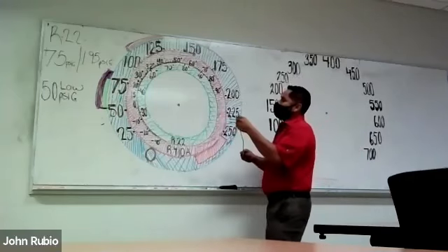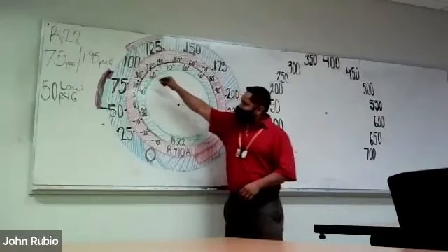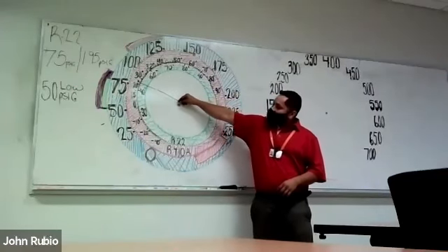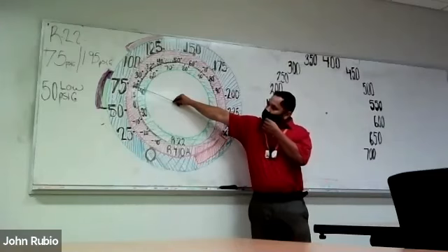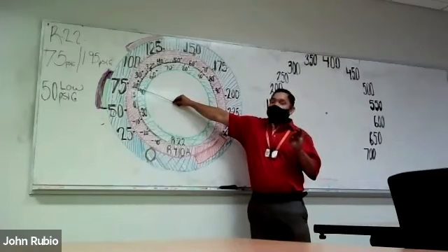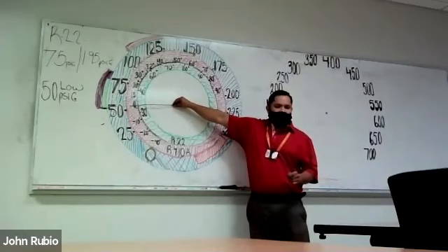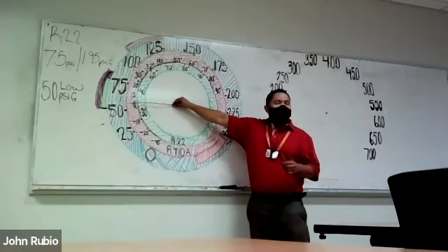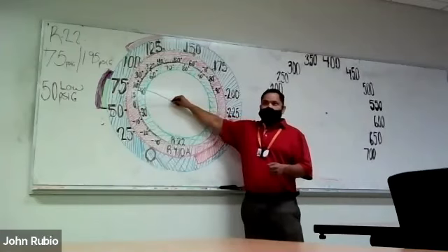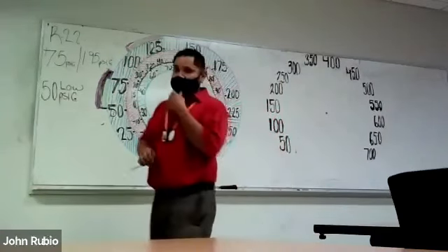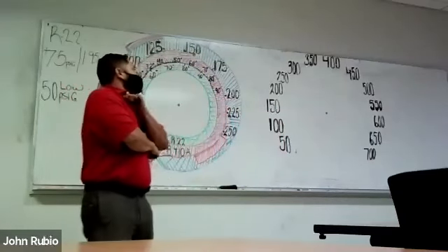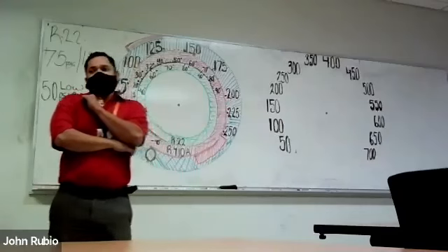What we need to understand is that when we're talking R22 that has a running pressure of about 75 psig, we see that when we drop to 50 psig, we induce freezing. But why? It's all about temperature pressure charts. Many times you'll hear, get your temperature pressure chart out. You'll need your temperature pressure chart. When we need our temperature pressure chart is when we are charging the system to subcool or superheat.